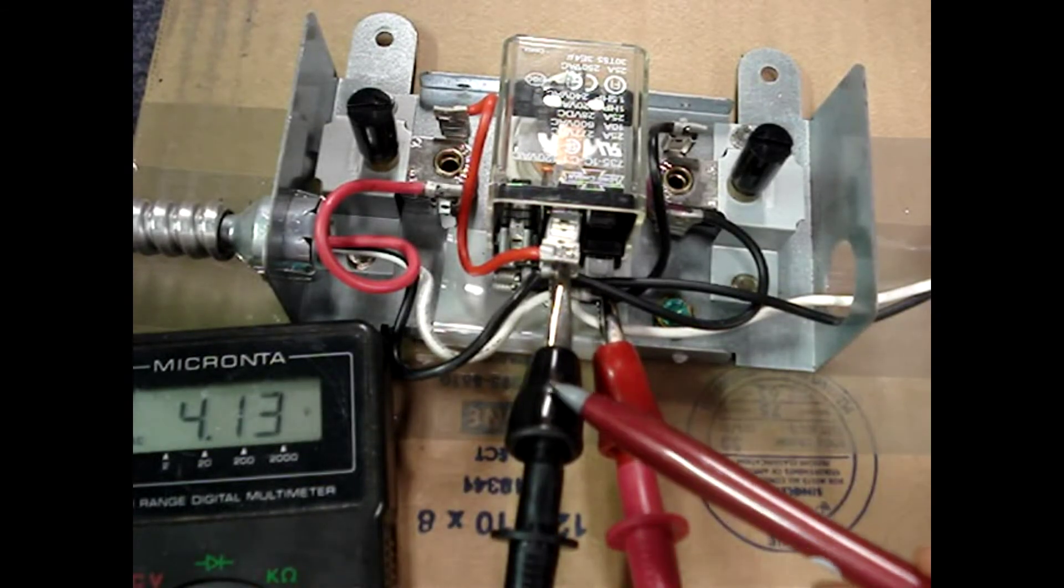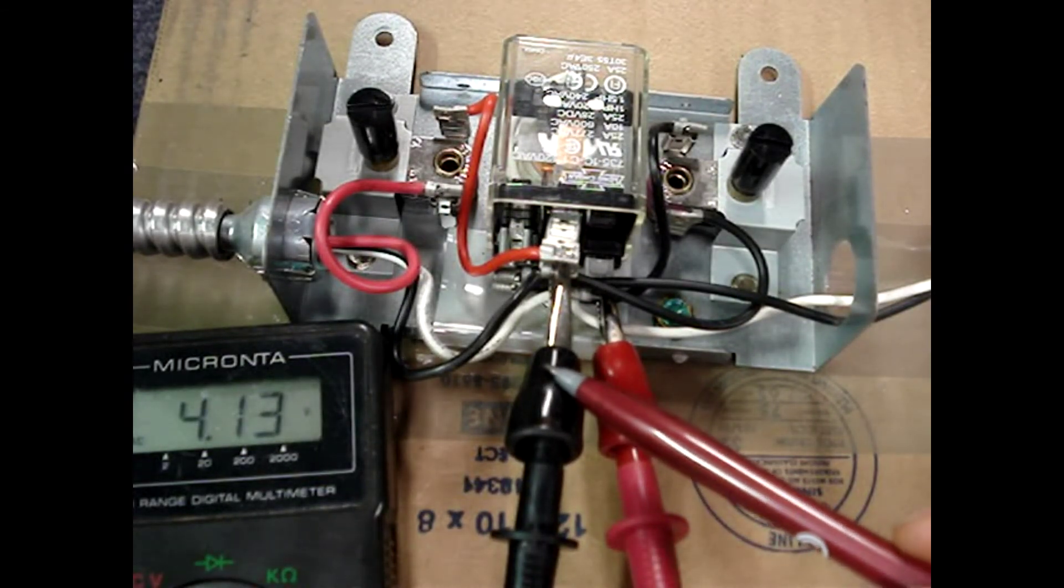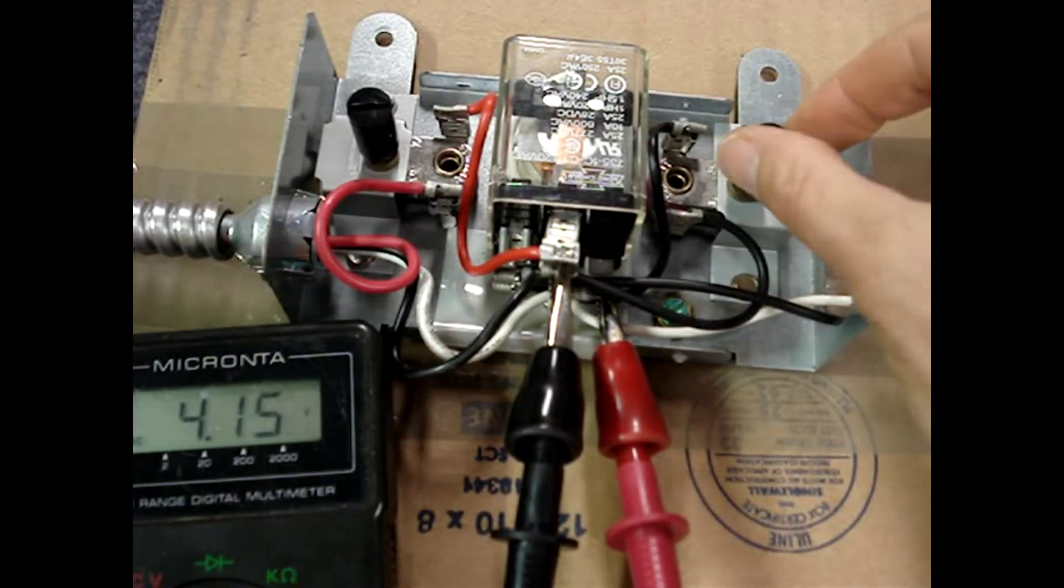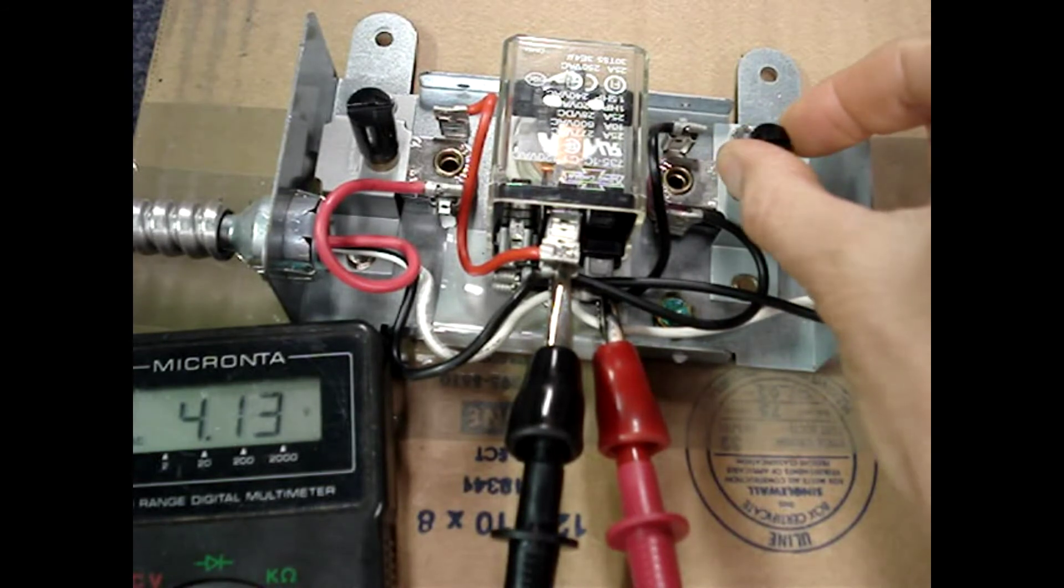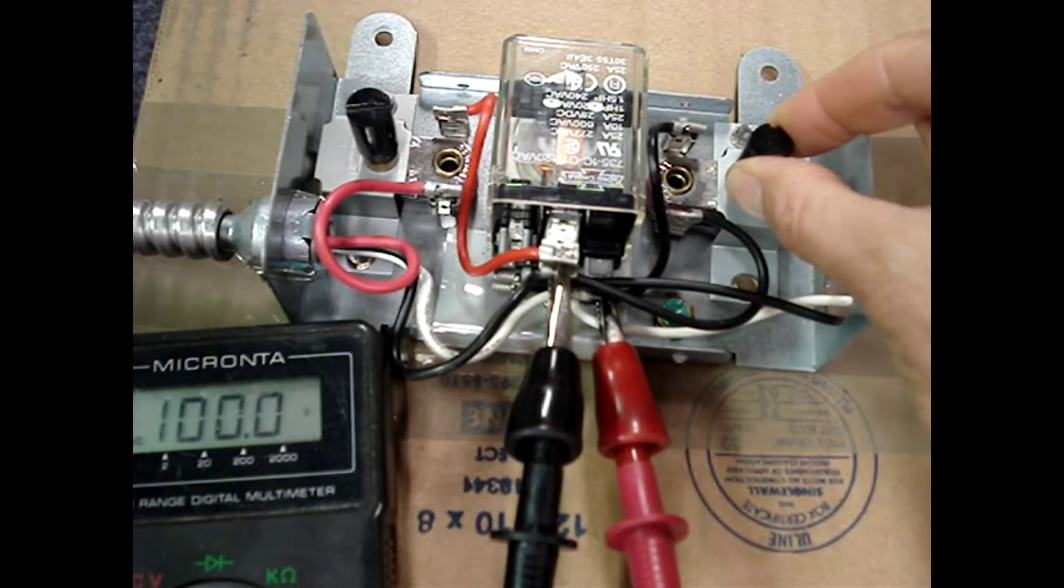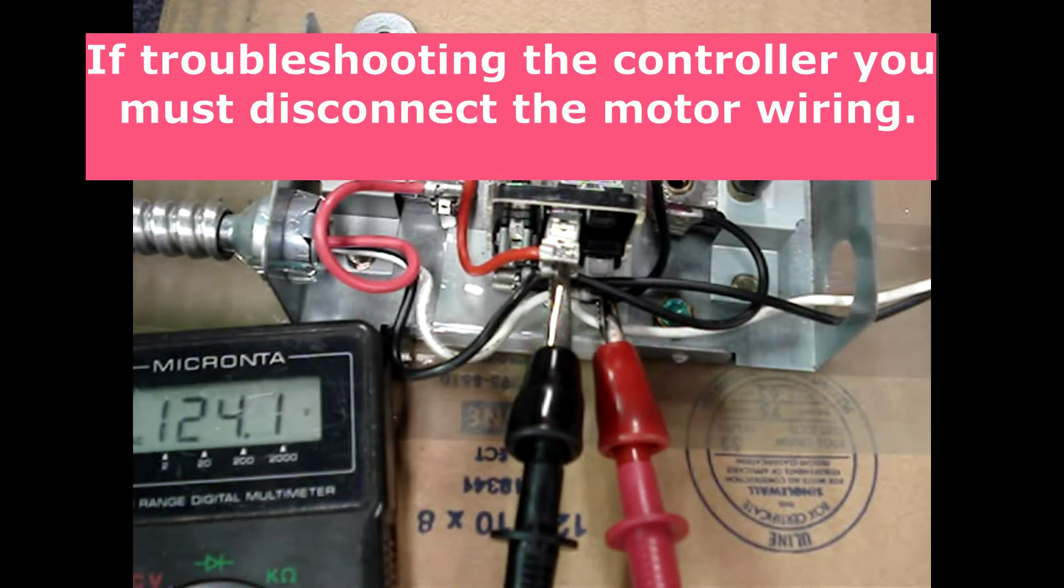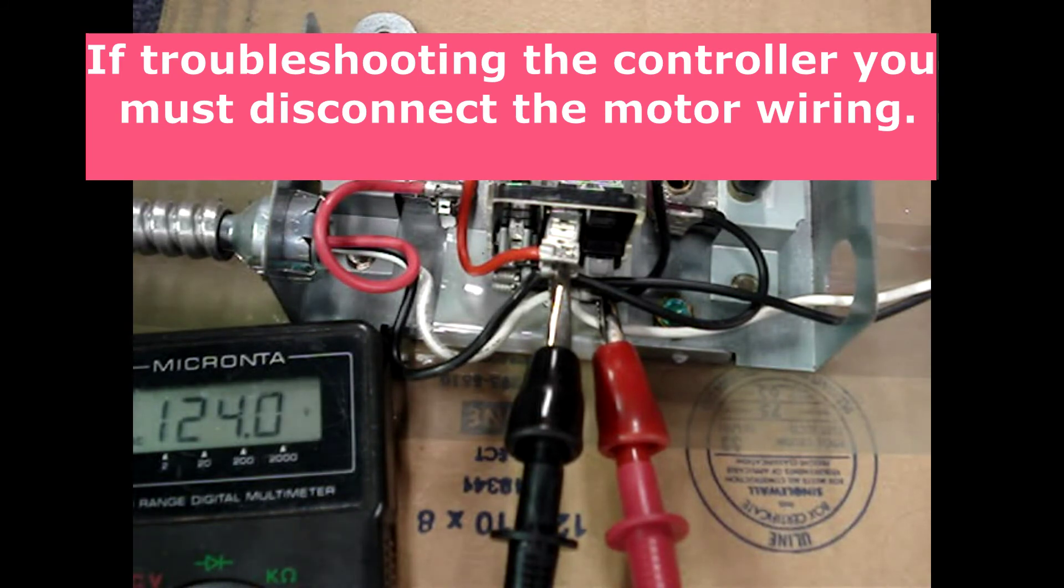I've switched my meter lead to the high speed fan winding. I'll simulate the attic temperature rising above 100 degrees and you could hear the relay click. The coils have energized and we now have 120 volts on the high speed fan leg.